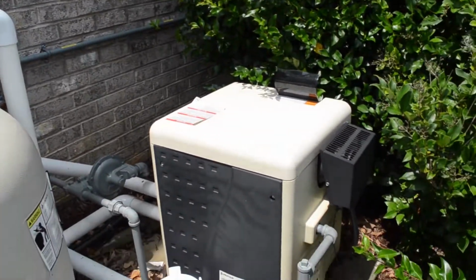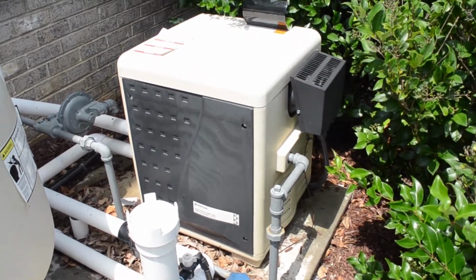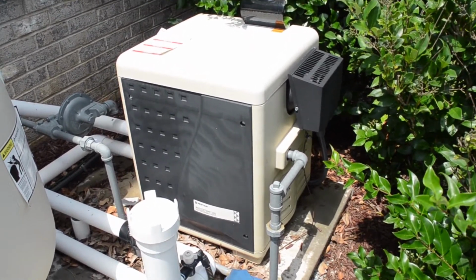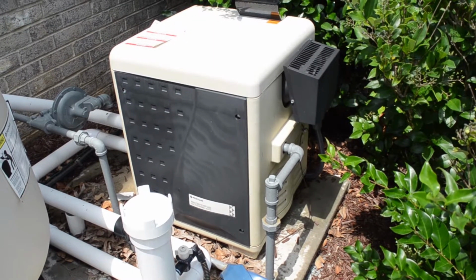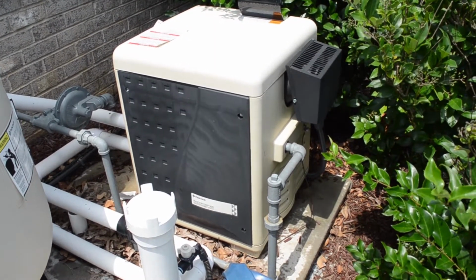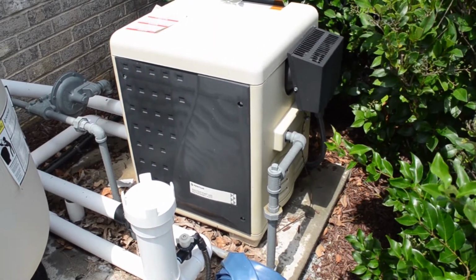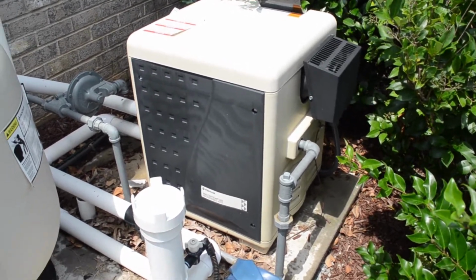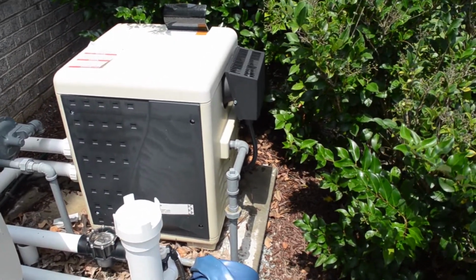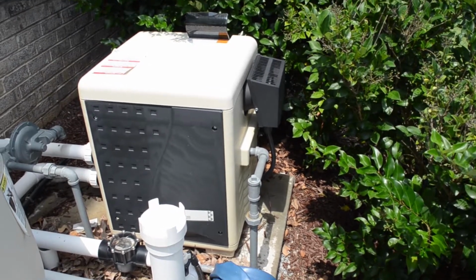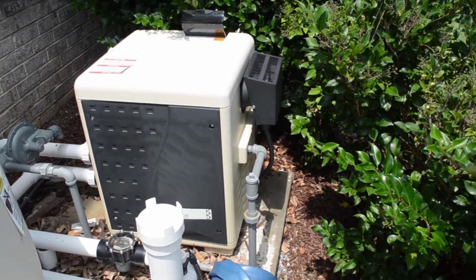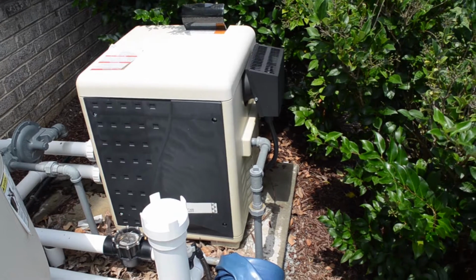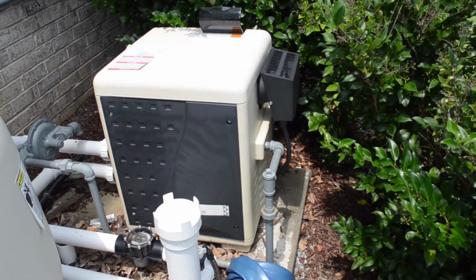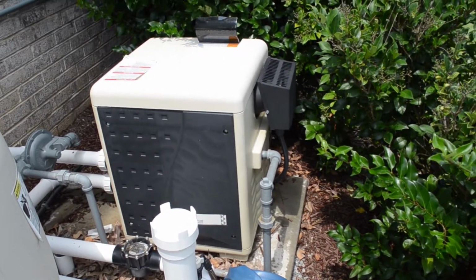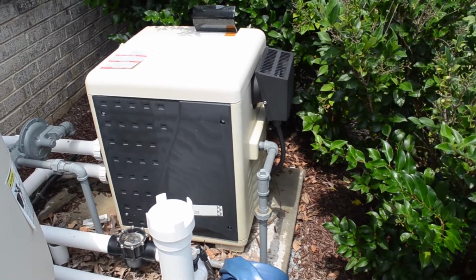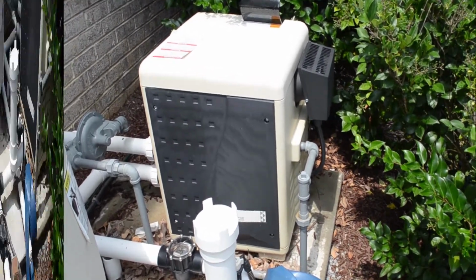And there's our heater. The heater does function - I had it running for a while and have since turned it off, but no problems with the heater. The only issue I have is how close the vegetation is. The exhaust gas gets extremely hot and could ignite the vegetation during a dry year, so I'd recommend they cut that vegetation back a couple feet from the heater.